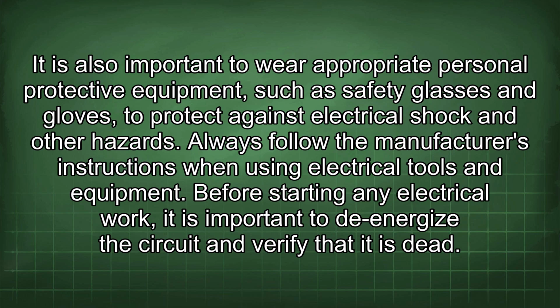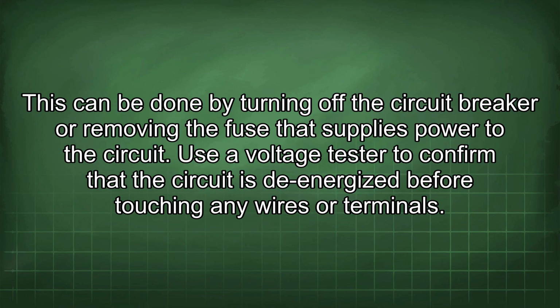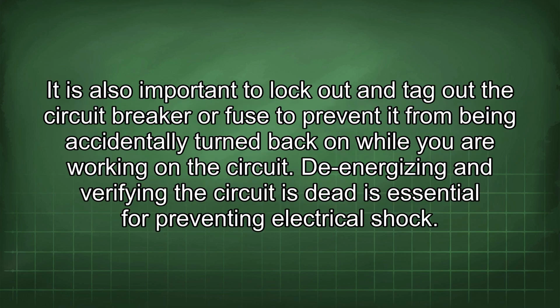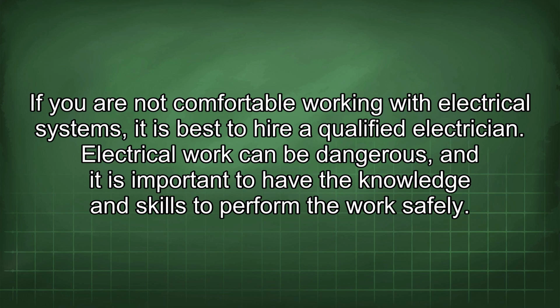Before starting any electrical work, it is important to de-energize the circuit and verify that it is dead. This can be done by turning off the circuit breaker or removing the fuse that supplies power to the circuit. Use a voltage tester to confirm that the circuit is de-energized before touching any wires or terminals. It is also important to lock out and tag out the circuit breaker or fuse to prevent it from being accidentally turned back on while you are working on the circuit. De-energizing and verifying the circuit is dead is essential for preventing electrical shock. If you are not comfortable working with electrical systems, it is best to hire a qualified electrician.